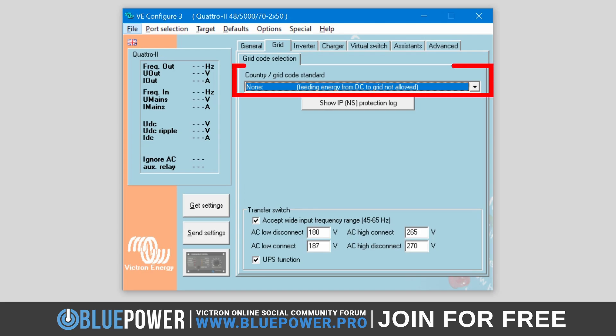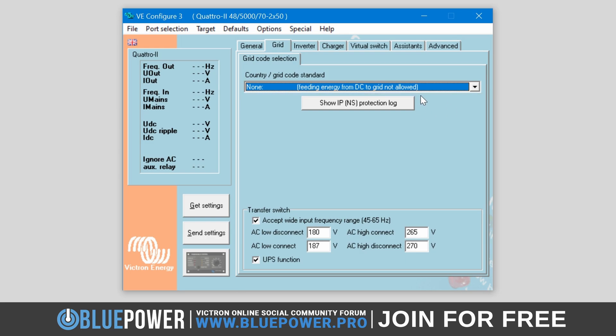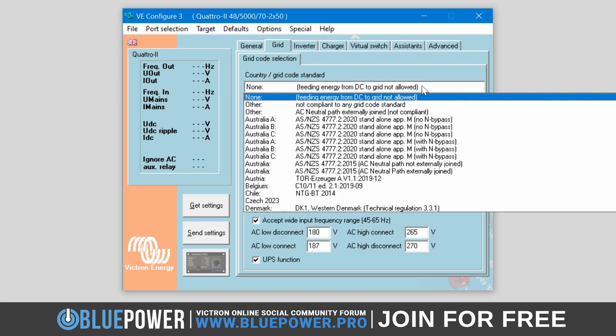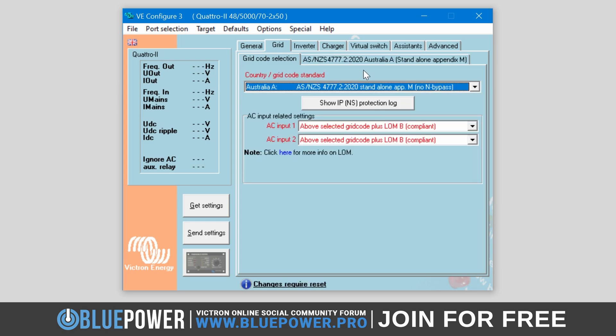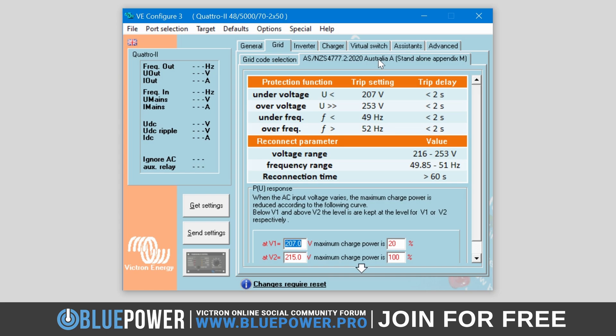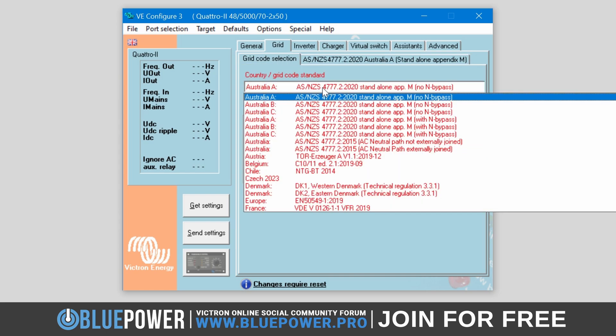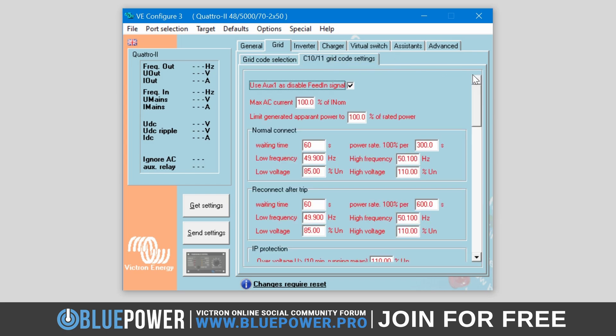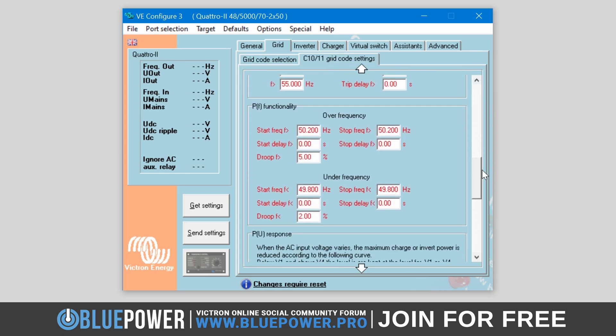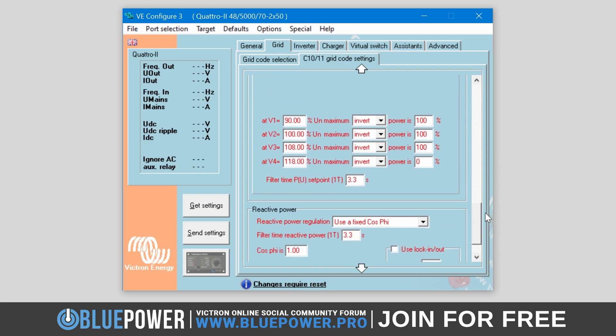The Country Grid Code standard setting is an important feature for configuring Victron's inverter chargers to comply with local grid regulations. Different countries have specific legislation and requirements for grid interaction, including how the inverter detects and responds to the loss of the grid, acceptable voltage and frequency levels, as well as ramp times. By selecting the correct grid code, it is set up to adhere to these local regulations, ensuring safe and legal operation.